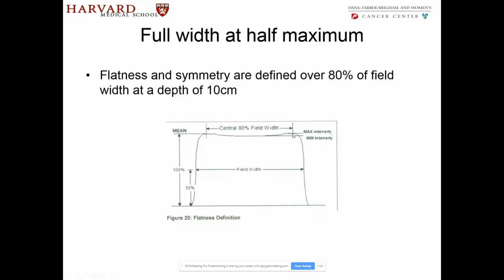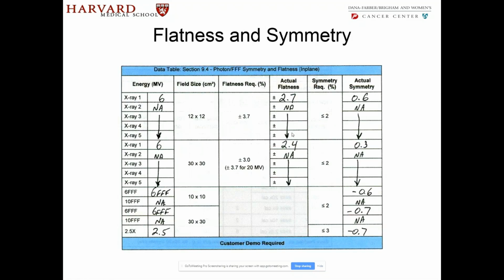So you measure the height here, you measure the height here, and check the difference. And that's where the flatness is defined. It has to be usually within 3%. And you can see, this is the sheet that you look at. Once the data is there, they analyze it through the software. Flatness requirement is 3.7.